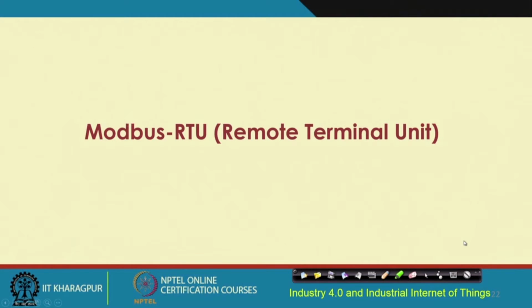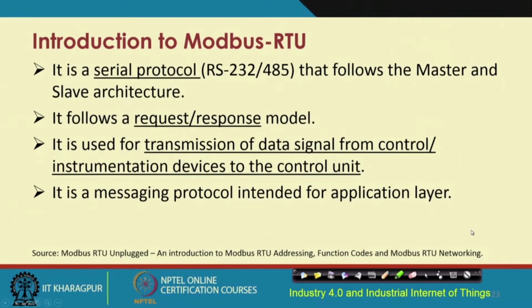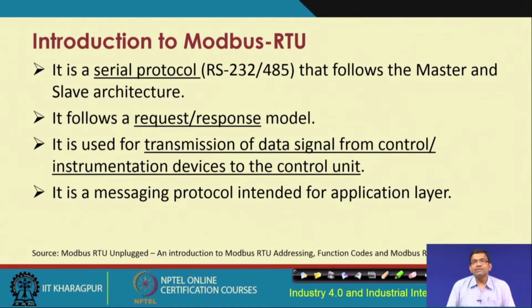Then comes the field bus protocol, which is the Modbus RTU. This Modbus RTU protocol is a serial protocol following RS 232 and RS 485 standards. So, it provides the serial communication between the master and slave and follows a request-response model. So, it is used for transmission of data signals from the control or instrumentation devices to the control unit.